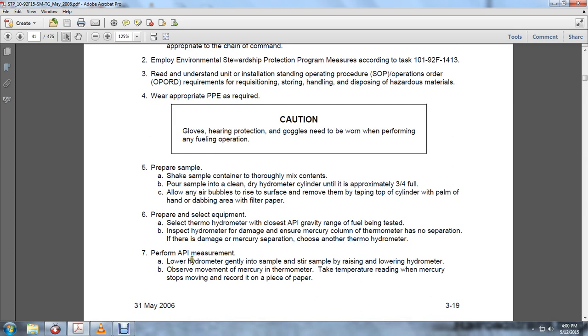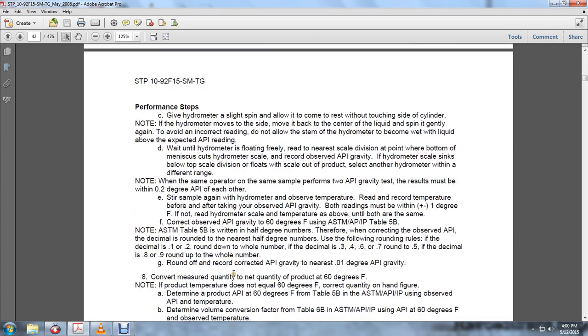Perform the API measurement. Lower the hydrometer gently into the sample. Stir the sample with the thermometer, observing the movement of the mercury. Take the temperature reading when the mercury stops moving and record it on a piece of paper. Give the hydrometer a slight spin and allow it to come to rest without touching the side of the cylinder. If the hydrometer moves to a side, move it back to the center and spin it gently to avoid an incorrect reading.